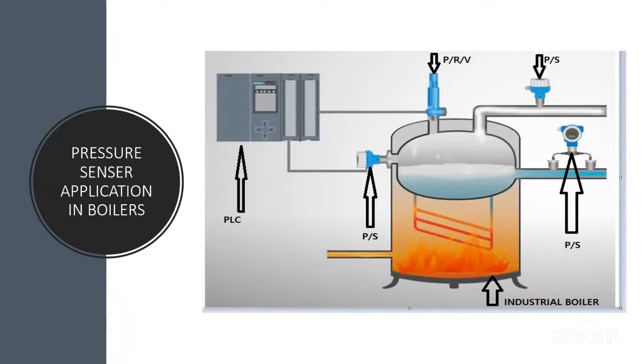In addition, it's actually not going to work alone; it's going to work alongside other equipment such as the modulating valve for steam. So when the pressure sensor senses steam pressure more than the required, whereas our intention is to send just about 5 bar to the destination machine, while the capability of the boiler is 8 bar, then we can tell the controller: when you see a pressure of about 8 bar, what you have to do is close the modulating valve about 75% so as to reduce the pressure of steam sent to the destination machine. These are various ways in which we can use pressure sensors in the case of a boiler like this in industry.